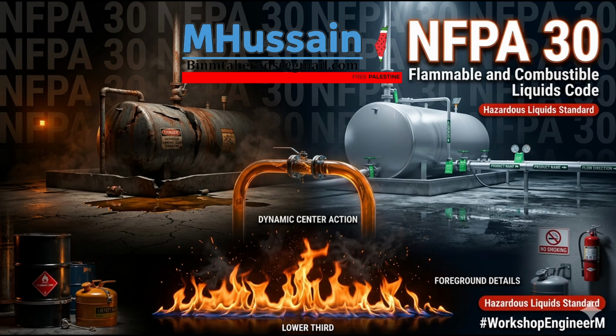Now, you mentioned closed cup flash point, and I want to pause there because engineers see that on safety sheets all the time. But the physical mechanism is so important. A lot of people probably assume you just hold a lighter over a puddle of liquid and see if it catches fire. Right, which would be an open cup test, essentially. But the closed cup method is way more precise, isn't it? It is entirely different. In an open cup test, the liquid is heated while exposed to the ambient air, so any vapors it makes can just drift away into the room. Which means you might get a falsely high reading of when it actually becomes dangerous.